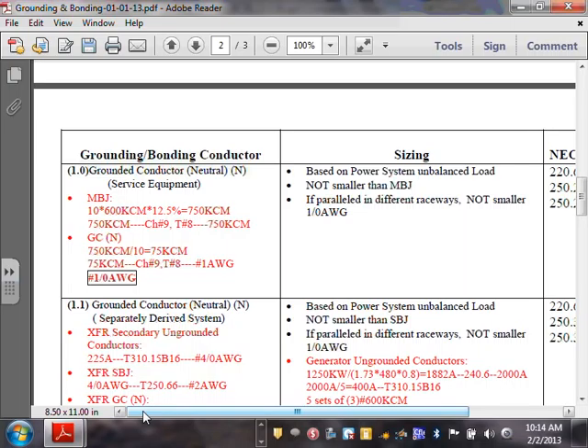So in this case, your main bonding jumper is going to be 750. Now, if you take the 750, guys, divided by 10, why did I divide it by 10? I have 10 runs, right? Divide this by 10, get you 75 kcm, right? You take the 75 kcm, take it to chapter 9, it gets you which number? 1. What's wrong with number 1? Too small. Not too small. You can't parallel it. So you cannot parallel it. So you have to go to 1 aught.